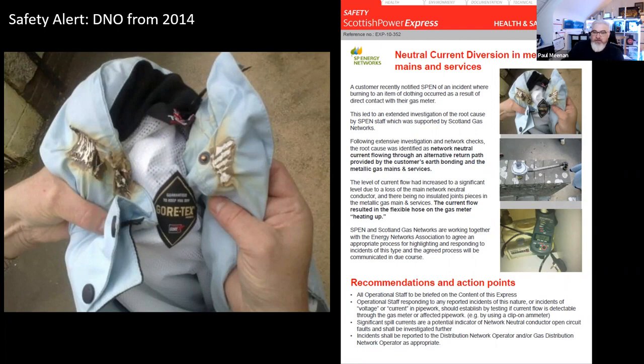On the ones that I've found, I've just recommended using clamp meters before you start working on any earthed equipment, just to measure and gauge what's going on, what's the behavior of the installation. As we saw earlier on, with a normal installation, when the installation's isolated, it shouldn't be a problem. If you isolate an installation and you find current flowing, then you might want to see why that is appearing in my installation. There's nothing coming from my fixed installation, it's coming from somewhere else, hence the term diverted neutral current.